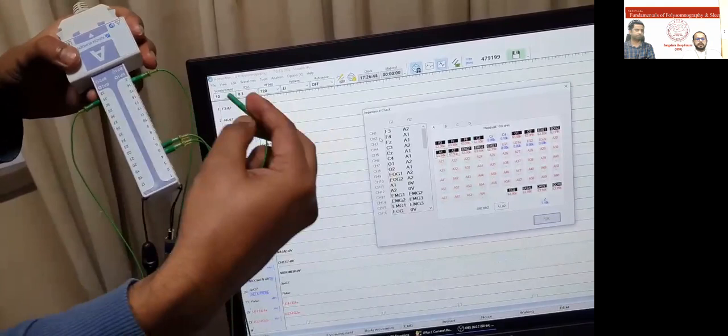So this particular window is the impedance window. Here we have connected 4 electrodes already. As you can see, once the contact is secure, it will show us an impedance rating. Our goal is to minimize the impedance as much as possible. Typically we can set the ranges as well. Here, it was pretty good. It's below 1 kilo ohm. Typically we try to keep it below 10 kilo ohm. That's why you can see the threshold is kept at 10 kilo ohm.